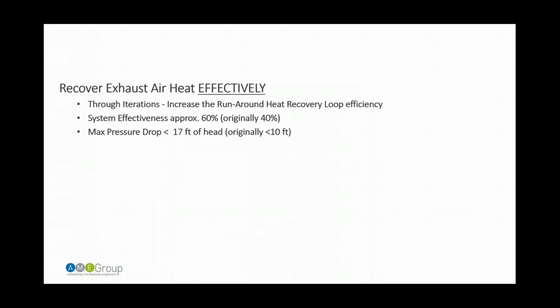And we did that through increasing our peak max pressure drop on the coils, which typically we'd want to keep around 10 feet. And looking at increasing that, we were able to get about 20% more efficiency on the system as a whole. And we didn't even have to go that high. We're still less than 17 feet of head on the runaround coils. And pumps on that runaround coil on VFDs, so that when we don't need the peak heat recovery, then we're operating at lower pump pressures all around the system. So that's where increasing that pressure really didn't affect us too much in terms of the overall energy savings.